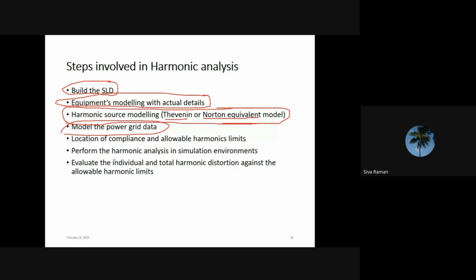Okay, and the next one is the location of compliance. Most standards and grid codes as of now specify the grid interconnection point as the compliance point. In the previous example we saw, the 10 kV point is the compliance point. At that location, we have to comply with the harmonic allowable limits. So we want to know the compliance location and the allowable limits in both voltage and current harmonics, including the individual harmonics as well as the total harmonic distortion or total rated current distortion.